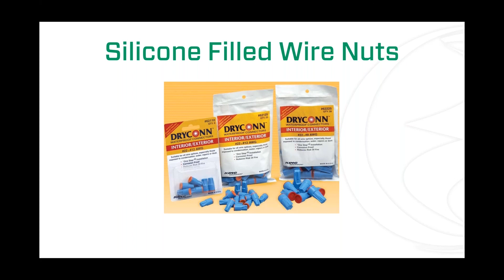But again, with a standard wire nut, you get sewer gases in there, and they will deteriorate over time. I've been to more than one job site where I've seen standard wire nuts actually burned or melted off, and I have seen very expensive pumps burned up because of a poor electrical connection or a bad wire nut connection, or one where these sewer gases simply got to a standard wire nut and it eroded or corroded away, and we lost a phase, we lost a connection, and the pump could not operate on the proper voltage, and we burned the pump up. So again, there are a lot of good reasons to use these silicone filled wire nuts. I think they're a superior system. I think that you should make this your standard practice and use them. And I'll also tell you to just carry a roll of paper towels in your truck with you, because they can get messy. So silicone filled wire nuts, good practice to use.